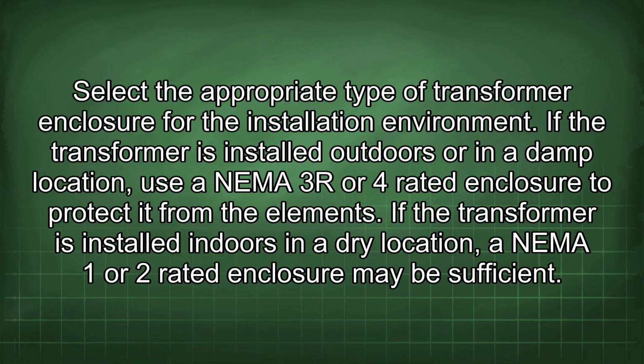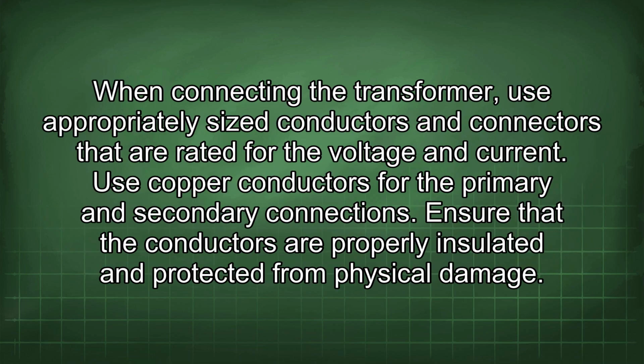Select the appropriate type of transformer enclosure for the installation environment. If the transformer is installed outdoors or in a damp location, use a NEMA 3R or 4 rated enclosure to protect it from the elements. If the transformer is installed indoors in a dry location, a NEMA 1 or 2 rated enclosure may be sufficient. When connecting the transformer, use appropriately sized conductors and connectors that are rated for the voltage and current.